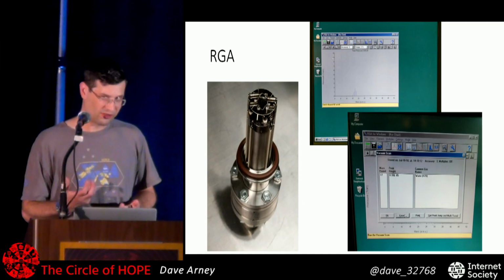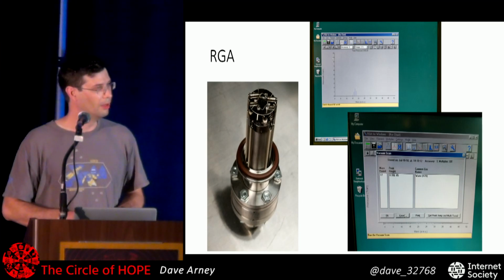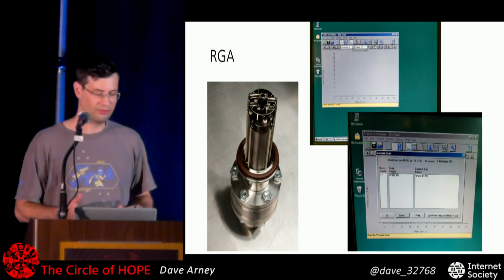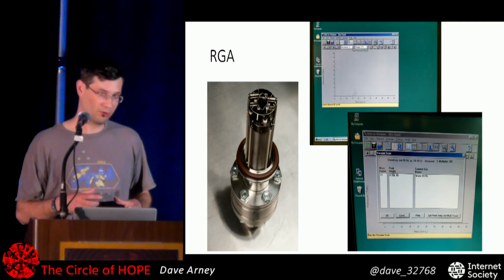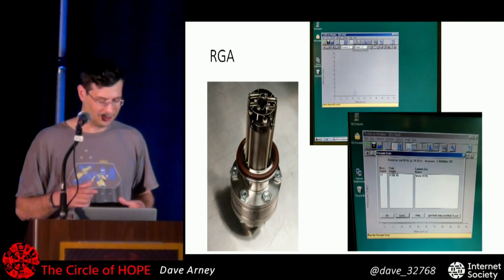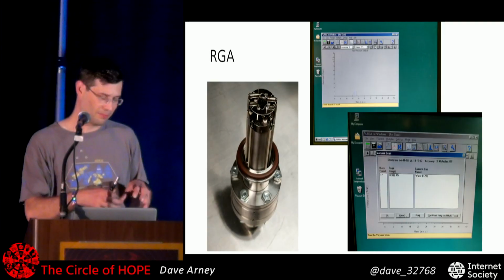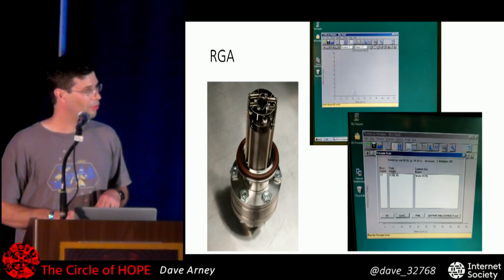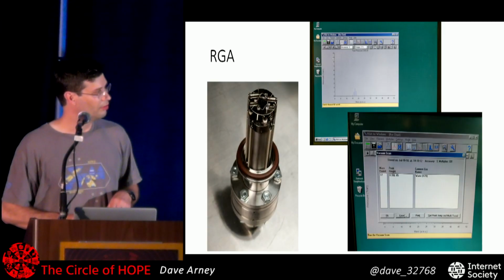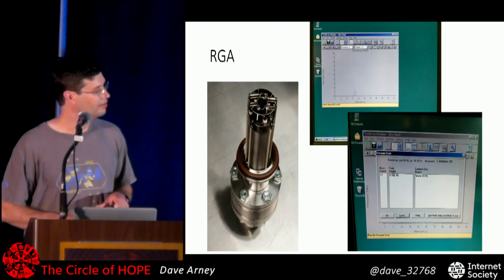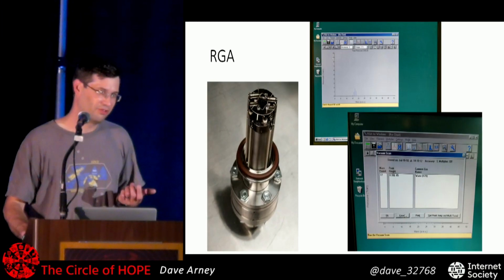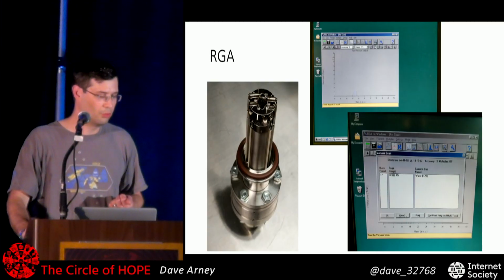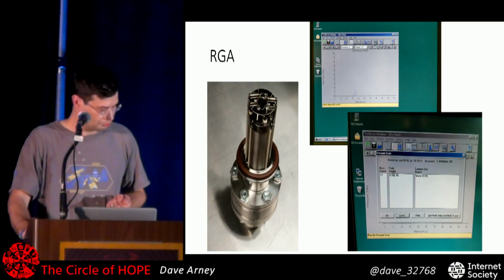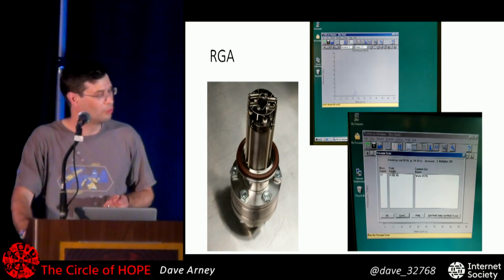If you want to know what's happening in the chamber, there's something called a residual gas analyzer. This is a small quadrupole mass spectrometer that sits in the bottom of the chamber, connects to some software that I got on 3 floppy disks. The documentation says it works well under Windows NT, but that they really recommend Windows 3.1.